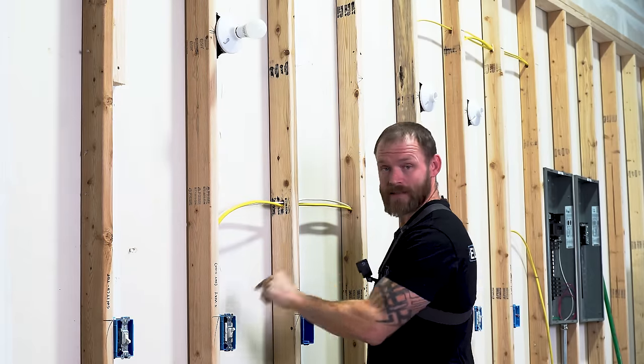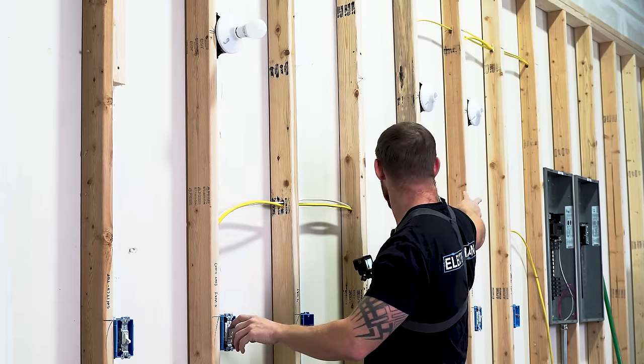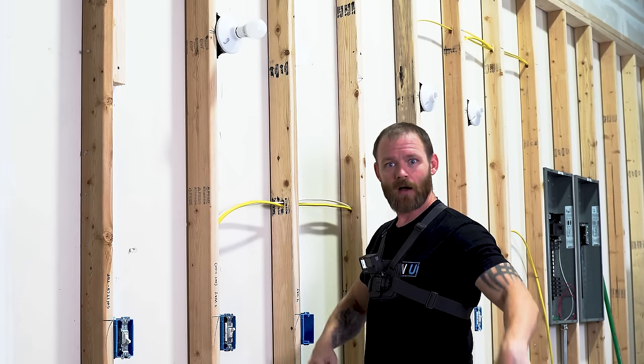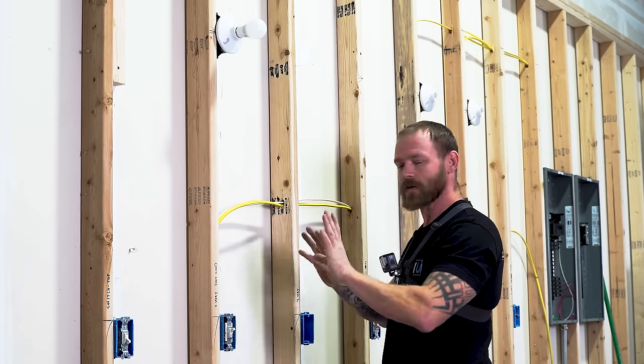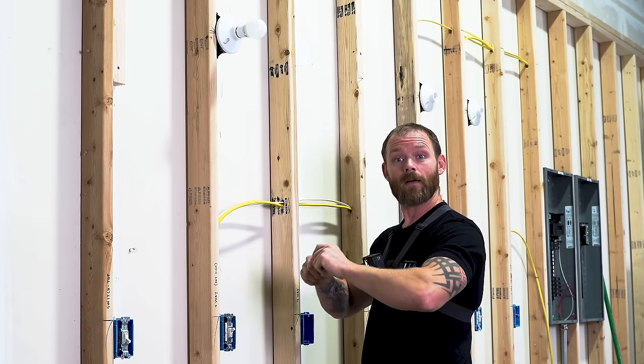A lot of times on the hot side, if there's a problem, you'll notice when you switch something on an entire room will switch on or like multiple rooms might turn off or turn on. It kind of depends on the situation, not always, but a lot of times with the hot, sometimes somebody will have wire nutted something together.